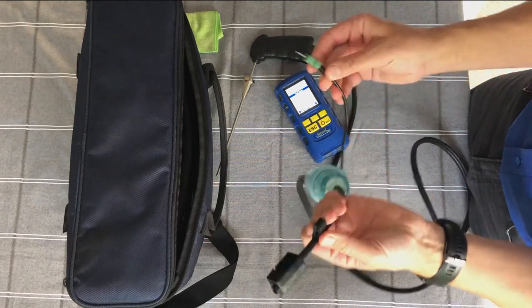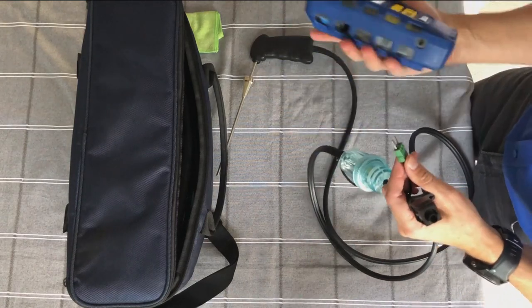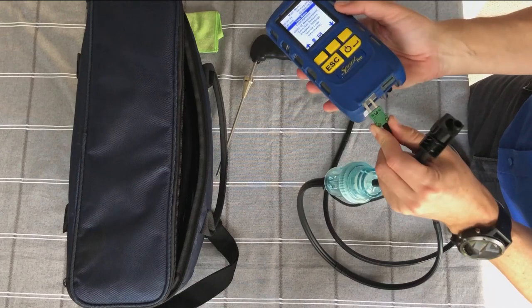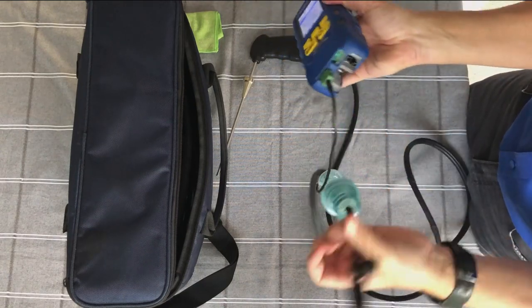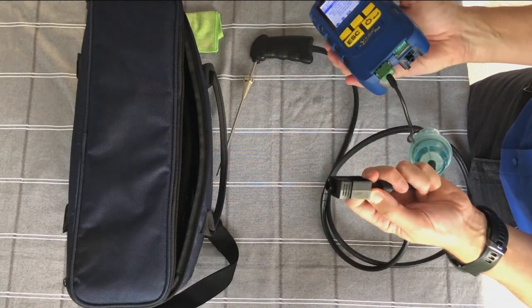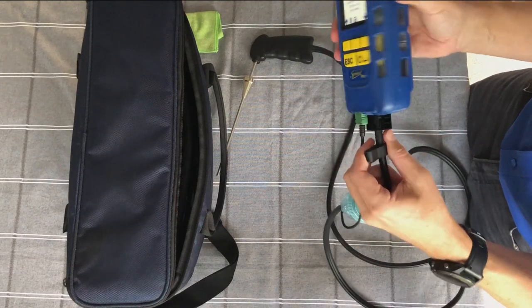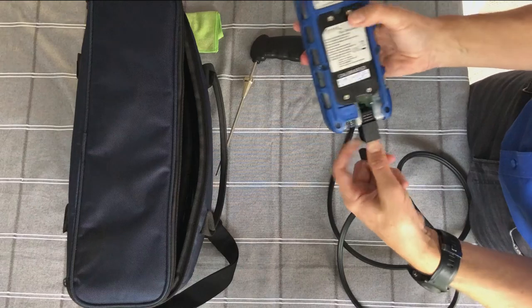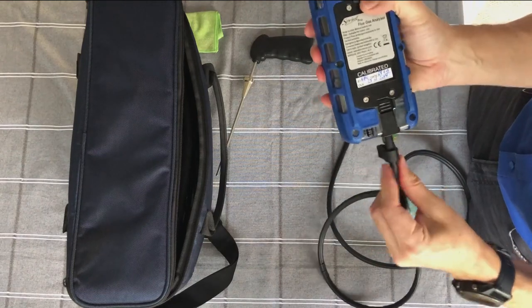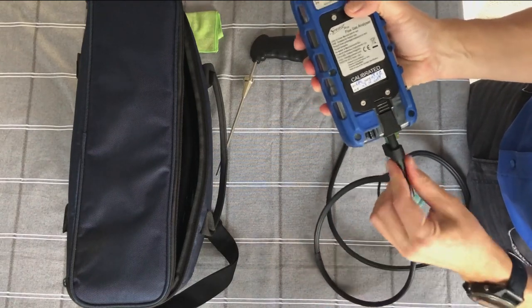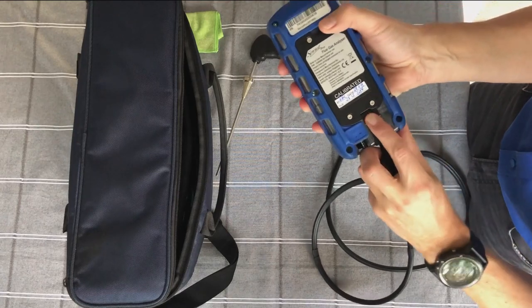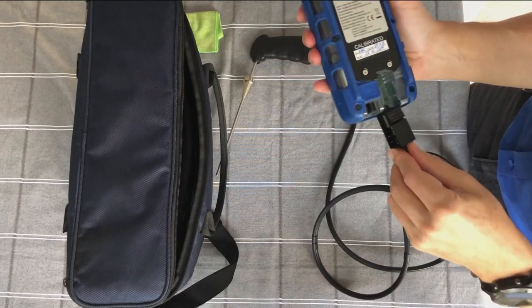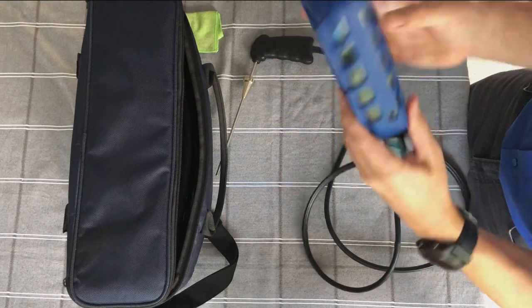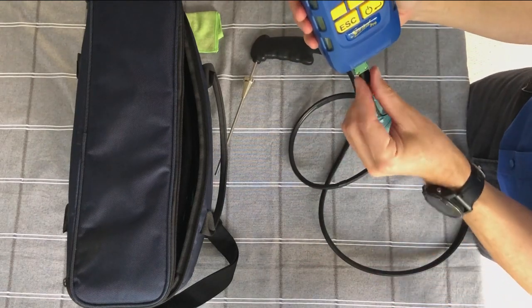This end we've got the thermocouple, so obviously when you're ready to use it for flue gas analysis, you plug that in. Doesn't matter which side, actually, you can plug it in either side. And then we've now got this connector, so this connects into the instrument like so, if you can see that, and it just pushes, clunks fit, and then I can't pull it out. So it stops it dropping off, little button to release it, but it clicks in like that, so you're now ready to start taking flue gas readings.